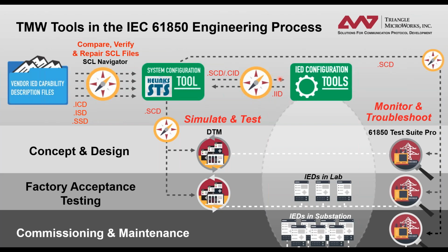So we found it's very valuable to have a third party and independent tool that can verify that SCL file against the standard, not only with a schema check, but a model check and validate against a lot of other details in the standard to make sure things are right. And that's another key role of the SCL Navigator, is to verify those files are completely correct before you get into integrating them.